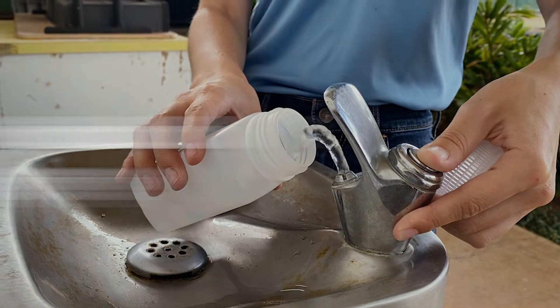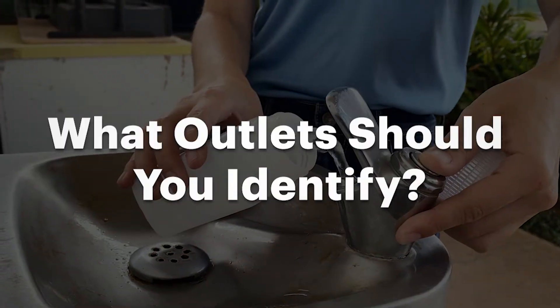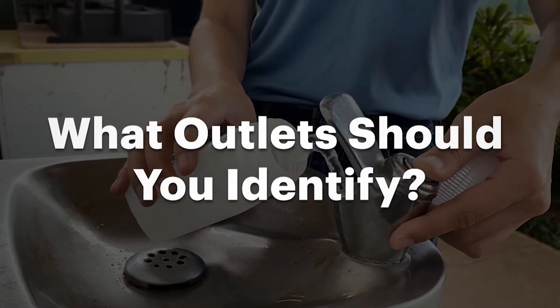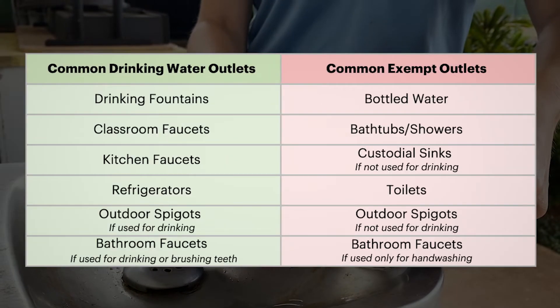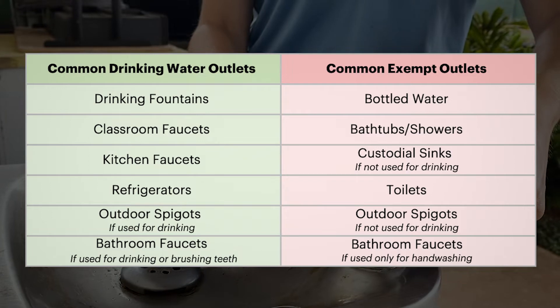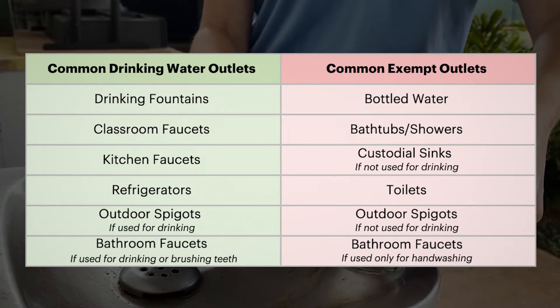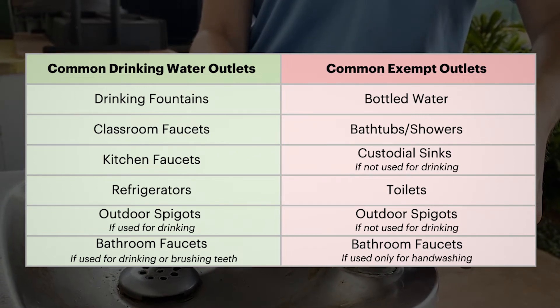So, what outlets should you identify? State law requires the testing of every location used for drinking or food preparation. This table provides an overview of common drinking water outlets. Don't forget sinks used to fill up coffee pots or spigots used to fill sports jugs on the playground. It's critical to identify every outlet used at your facility because lead levels can vary greatly between fixtures.